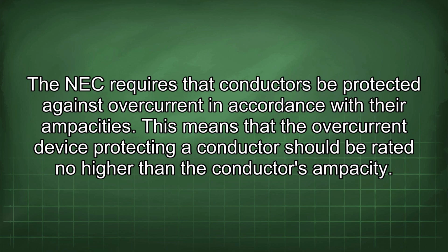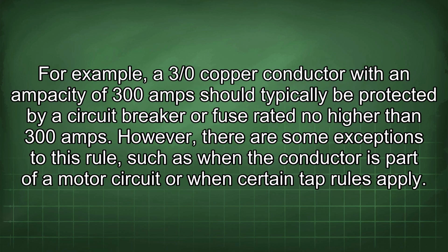This means that the overcurrent device protecting a conductor should be rated no higher than the conductor's ampacity. For example, a 3/0 copper conductor with an ampacity of 300 amps should typically be protected by a circuit breaker or fuse rated no higher than 300 amps. However, there are some exceptions to this rule, such as when the conductor is part of a motor circuit or when certain tap rules apply.